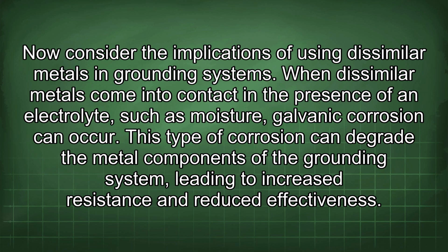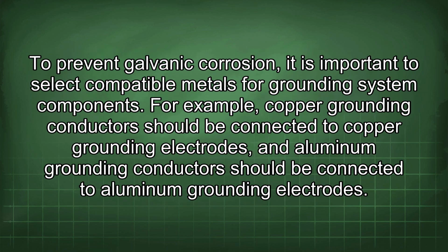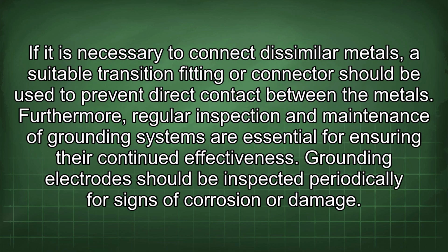When dissimilar metals come into contact in the presence of an electrolyte, such as moisture, galvanic corrosion can occur. This type of corrosion can degrade the metal components of the grounding system, leading to increased resistance and reduced effectiveness. To prevent galvanic corrosion, it is important to select compatible metals for grounding system components. For example, copper grounding conductors should be connected to copper grounding electrodes, and aluminum grounding conductors should be connected to aluminum grounding electrodes. If it is necessary to connect dissimilar metals, a suitable transition fitting or connector should be used to prevent direct contact between the metals.